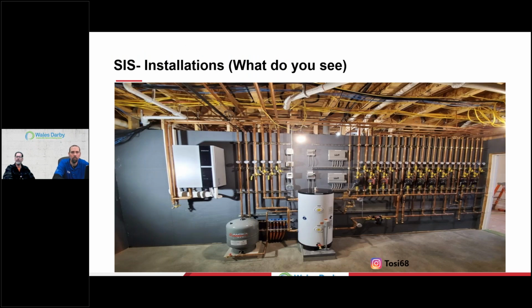There's a lot of pumping and piping going on here. There's a buffer tank or expansion tank, a lot of zones here with circulators. Nothing's insulated, so it leads me to believe that this is for heat only, unless they're going to come back and insulate all and everything exposed. Because if this was a reversing cycle, cooling to heating, it's going to be a swimming pool on that floor. So just be aware, when you are using a chiller or heat pump for cooling in warm ambient air, Mother Nature takes over and condensation will form. Just be cautious.